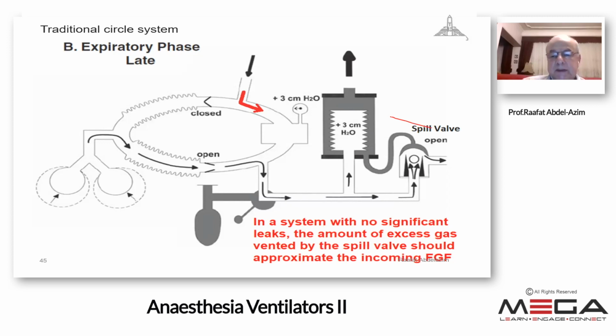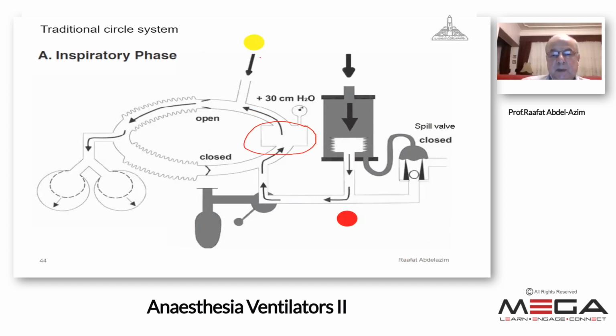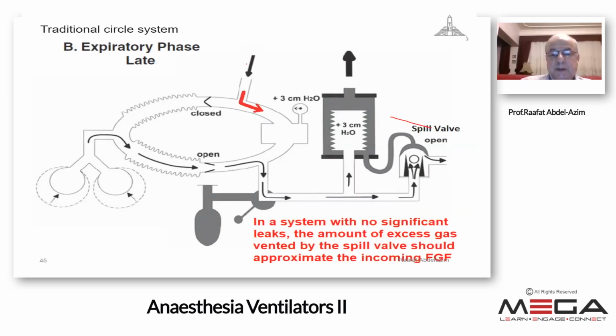We call it excess because all the time during inspiration, the fresh gas flow will go to the patient, and during expiration, the fresh gas will go into the spill valve. So the contents vented by the spill valve in a system with no leaks equals the fresh gas flow.